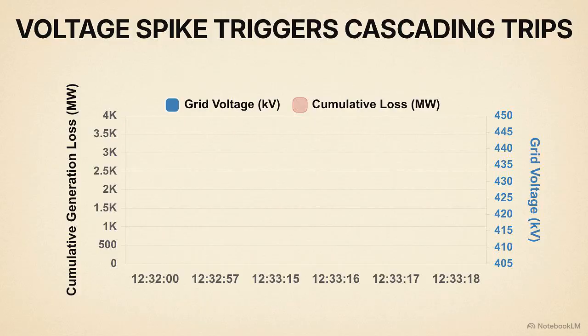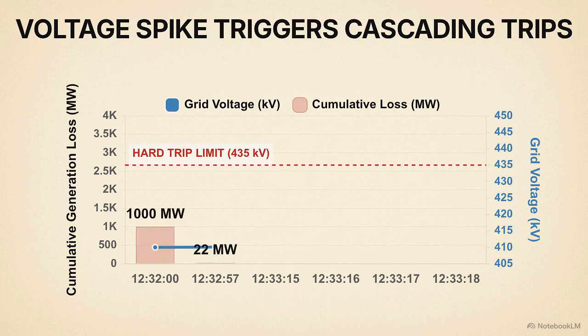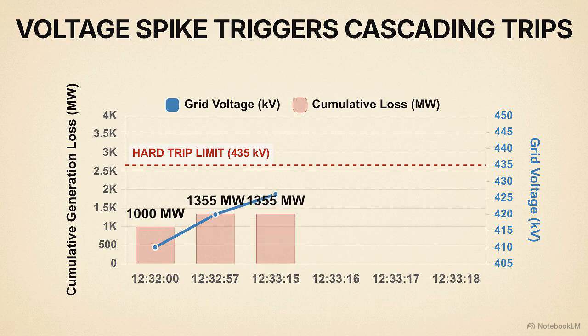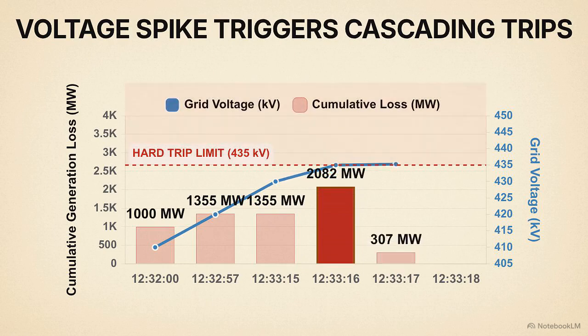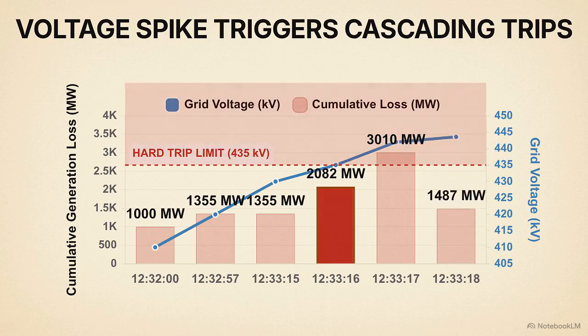This dual-axis chart demonstrates the direct correlation. As the rising voltage breaches the 435 kilovolt limit, it triggers a massive cumulative loss of generation megawatts as protections engage. Tracking the timeline forward to 12:33 and 16 seconds, over 727 megawatts of photovoltaic and thermosolar generation simultaneously tripped offline in the Badajoz area.